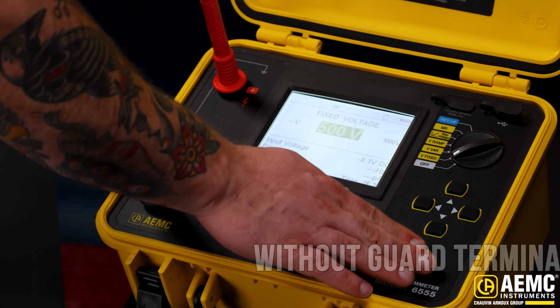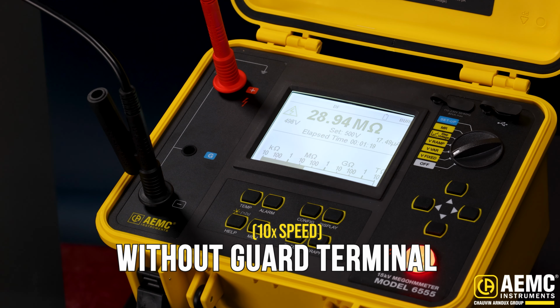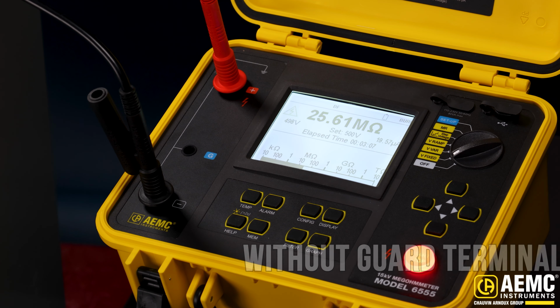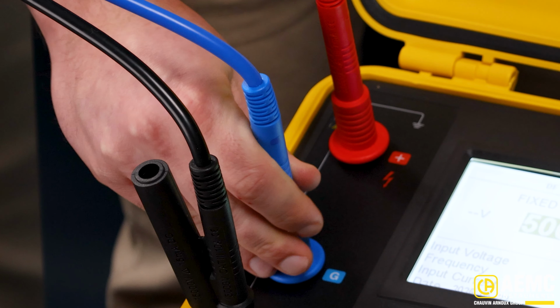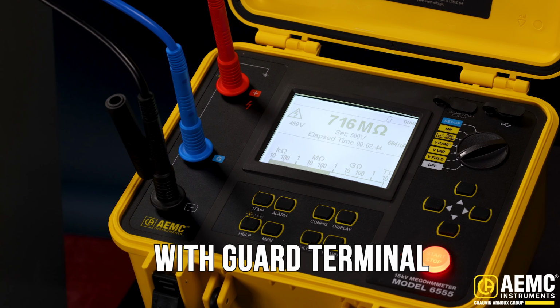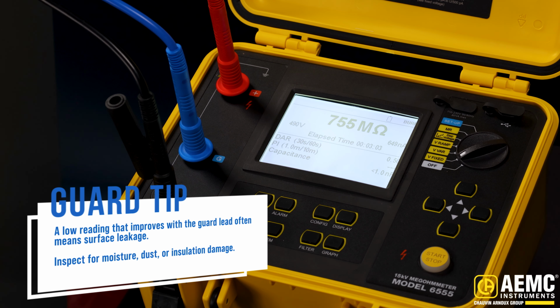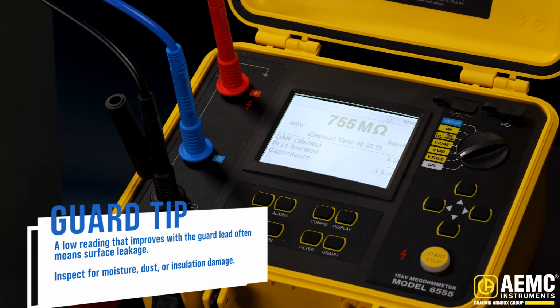Here's a test without the guard terminal with a resistance of about 25 mega ohms. Now with the guard terminal properly connected, the insulation resistance is over 700 mega ohms, a substantial difference that may warrant further inspection to ensure the integrity of the insulation of this transformer.